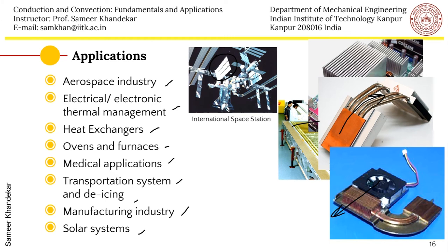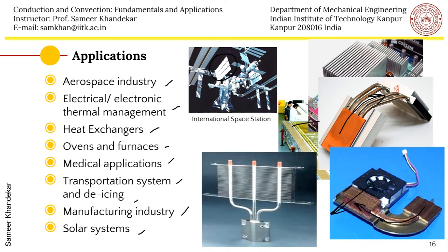Here again you see an IGBT cooler, three heat pipes, two of them are bent and one of them is straight. And again, you can see this is a very small area where the heat is collected from the IGBTs, and then this goes to the large area here. So naturally there is air flowing over here. The area outside is much larger, so the heat transfer coefficient H1 is high and the area A1 is small, and here the H2 is small and A2 is large. So in this way heat is getting transported from location A to location B very efficiently.